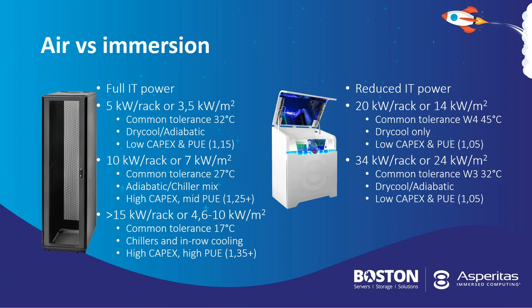So I've made a comparison between air infrastructures and immersion based on Asperitas technology. If you look at an air-cooled rack, an average deployment of an air system right now in an average data center you can walk into, nothing specialized yet, on average we're looking at a design capacity of approximately 5 kilowatts per rack. If that data center is fully equipped, completely filled, you can calculate that to a white space density figure of approximately 3.5 kilowatts per square meter. That is something we call the solution footprint.